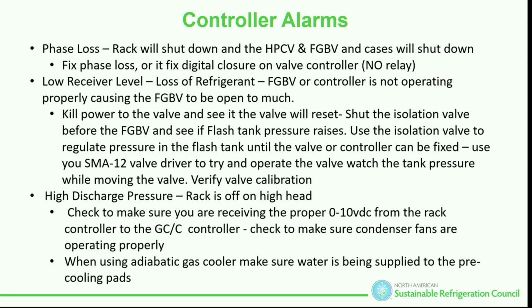I can't see it. I simply look at my controller. Look at my pressure. Am I opening? Am I making a change? That's going to tell me if it's opening or closing. So I'm going to do all that. Well, we've got high discharge pressure. The rack is off on high head. Oh my God, how many reasons could that be?